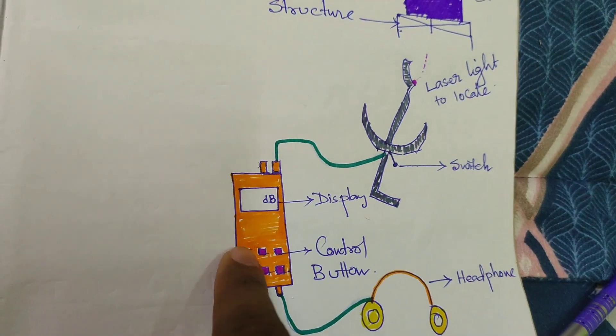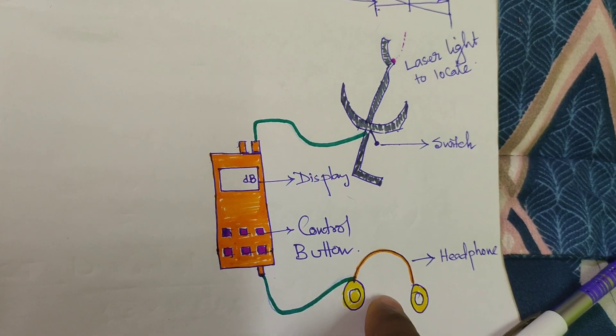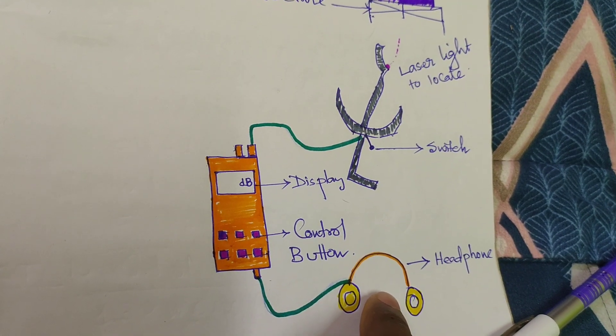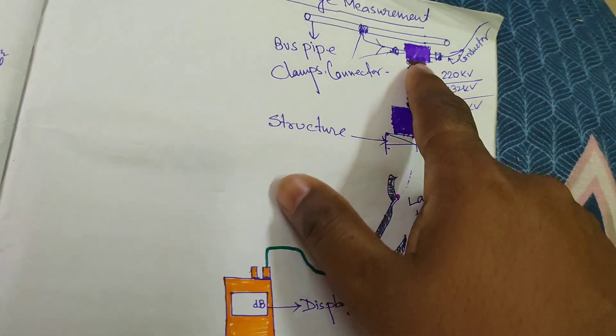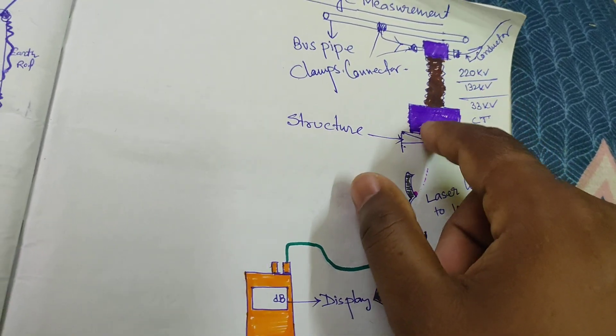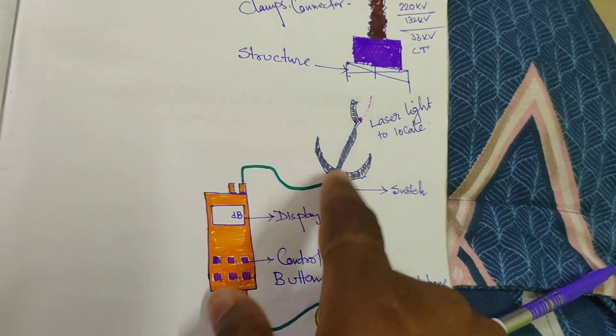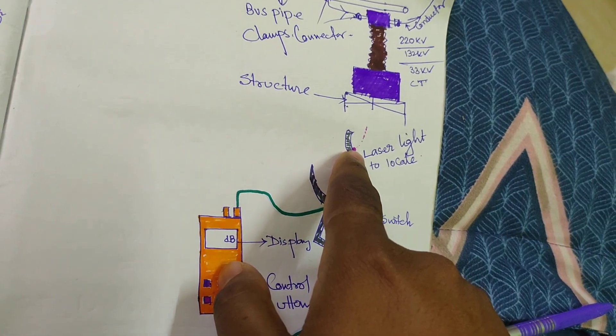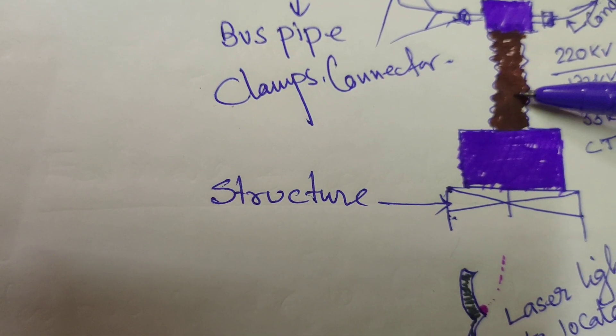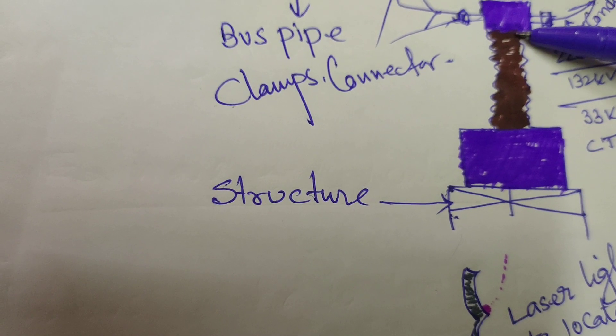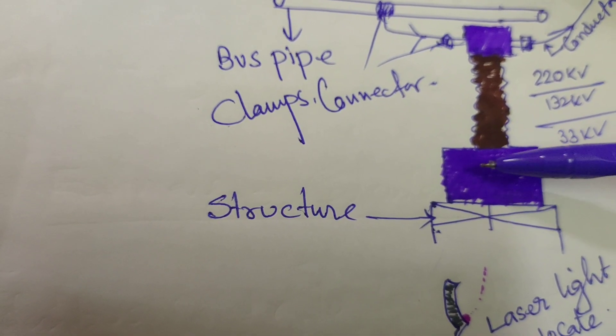Hold the gun in your right hand and the machine in your left hand. Press the switch after switching it on and wiring the headphone properly to your ear. You cannot hear outside sound — only partial discharge sounds come through. If partial discharge is present in insulating parts or any wires in electrical equipment, press the switch and the laser beam locates to the required position. Start from one point and gradually change positions, measuring PD at each point.